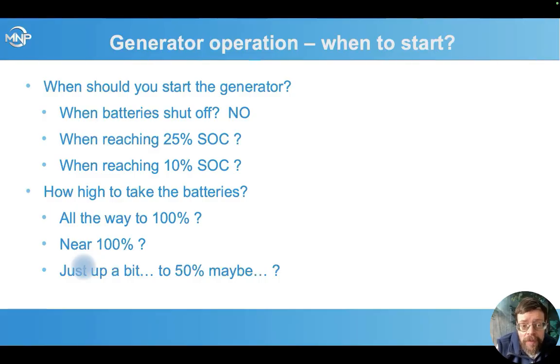Lithium batteries, we can go pretty low, but when should we start the generator? 25%? 10%? A lot of people really want to get the absolute maximum out of the batteries and try to take them as low as possible. But the problem with this is that what if that state of charge is not 100% accurate? Like I said, the state of charge can drift from reality depending on how long it's been since it's been at 100%. So if we're going to wait till 5 or 10% to start the generator, is that really 5 or 10%? Or do we have a 10% error and it's 0% before we started it, and now we have a black start situation?